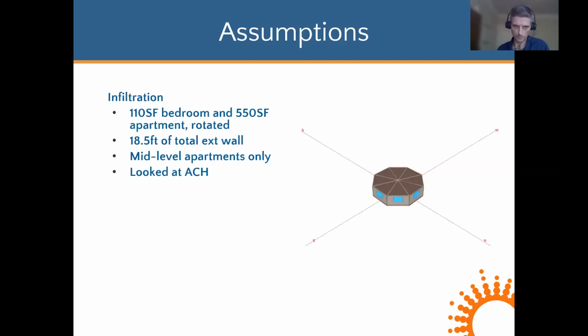All right, and then we built a 3D model using eQuest simulation software. We built a model for an apartment of 550 square feet, with a 110 square foot bedroom, and a total of about 18.5 feet of exterior wall length. We only looked at mid-level apartments, so we didn't look at infiltration from the roof or the floor. And we looked at air changes per hour for infiltration, which allowed us to build the apartment and rotate it around 360 degrees and then apply a weather file to it. And that weather file had actual wind speed and direction. And so we were able to take an average wind speed and direction and find an hourly average.